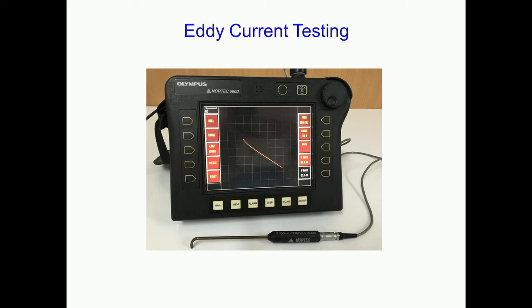As a system, this is very easy to operate. That is how the system looks, and if you take a close look, this is the display, and you can see a curve over here, which is the lift off curve that we have talked about. When you touch the probe on the sample surface, this is what you see. This is the beginning point, which is the point in air, also called the null point, as I am going to show you in the video also.